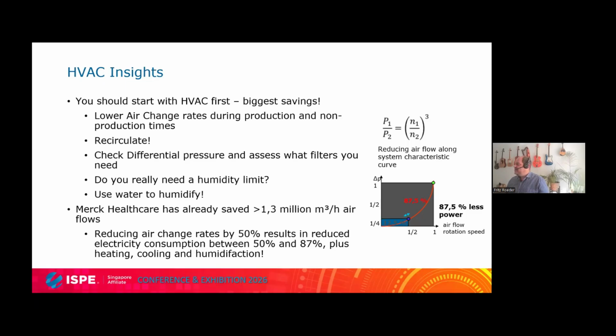Then adiabatic humidification of the exhaust air is a topic. So there are numerous ideas. Or one other topic, I've said this already for the warehouse: reduce the air changes just to meet the cooling loads in summer, or when it's hot. In Southeast Asia, it's always hot. Okay. And I can tell you that we've already saved at our sites 1.3 million cubic meters per hour of airflow. So this is a mid-sized sterile facility that we've basically shut down, to compare it.